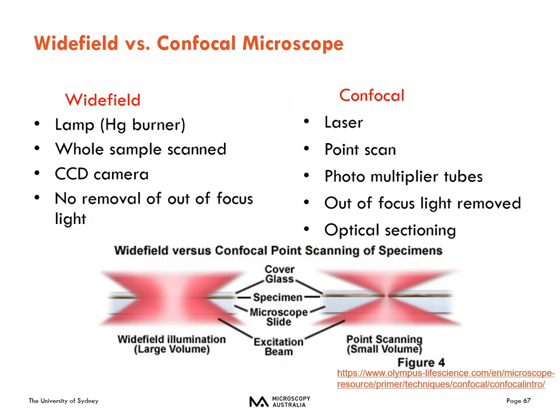Comparing wide-field versus confocal microscopy: wide-field uses a lamp (like mercury or LED) illuminating the whole sample simultaneously and uses CCD cameras, with no removal of out-of-focus light. Confocal uses lasers and raster-scans a point across the sample — talking about pixel dwell times of around two microseconds per pixel — using individual photomultiplier tubes. This achieves optical sectioning by eliminating out-of-focus light.